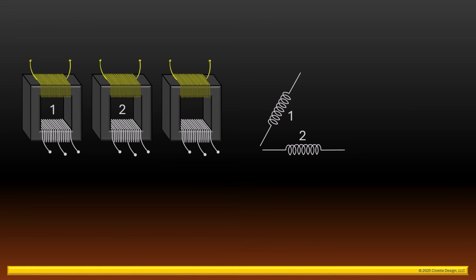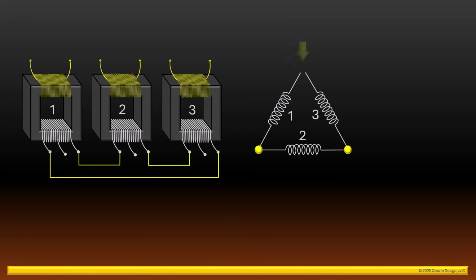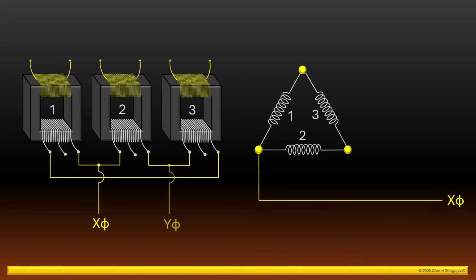We'll connect those together with a short jumper wire. This is symbolically shown on the right with a little dot connecting the inductor symbols together. We'll include the secondary winding of transformer number 3 and connect that to number 2 with another short jumper wire, also shown on the right. We'll add the long jumper wire connecting the outer leads, which also completes the triangle on the right. We add the X-phase lead to the jumper on the left, which is also shown on the right. We'll connect the Y-phase lead to the other short jumper wire.